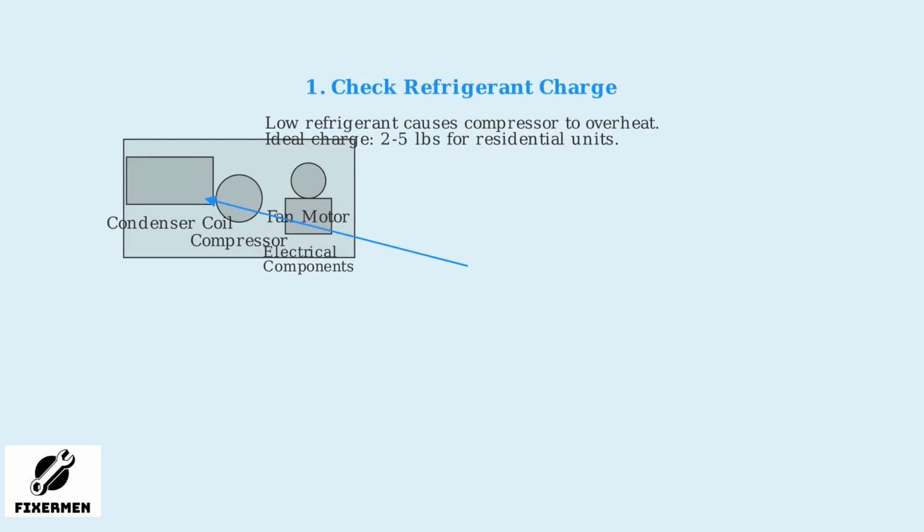This error indicates the compressor is working harder than it should, often due to refrigerant issues, airflow obstructions, or electrical faults. As of April 2026, newer Goodman units have integrated advanced diagnostics and can send alerts to the user before full shutdowns. Diagnosing an E4 error involves checking several key areas.